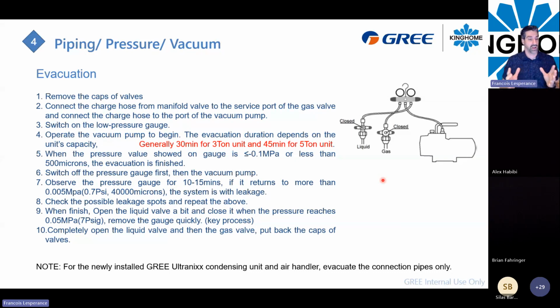Generally, it won't take a long time because it's only in the piping, so you don't have to bring the coil to 500 microns. It's only in the piping, so it's very fast. Also, when you hit 500 microns, close the valve, close the vacuum pump, and hold it for 10 to 15 minutes. If the micron on the gauge increases and never stops, and you break the 2,000 micron barrier, then you have a leak. If you are not able to hold the micron below 1,000 for 15 minutes, it's because you have a leak.